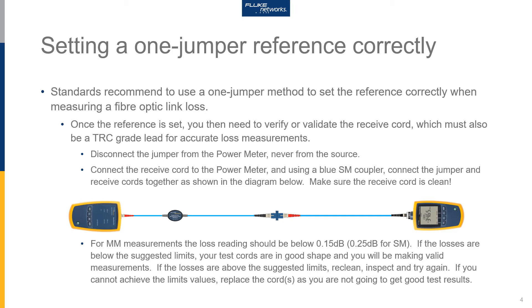Make certain the receive cord connectors are clean before connecting. Once you have the jumper cord and receive cord connected together, you'll be able to measure the loss of the mated cords. For multimode fiber measurements the loss reading should be below 0.15 dB. If you're validating single mode cords, the loss reading should be no more than 0.25 dB. The extra 0.10 dB allowed takes into account field conditions. If the measured results are below our suggested limits, your cords are in good shape and you will be making valid measurements.